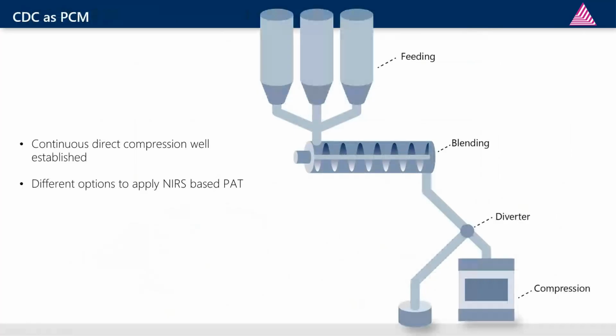We'll focus mainly on the continuous direct compression applications. They are very widely used meanwhile in the industry, and they get the most of the attention in the industry. I would not say there's still a lot of granulation and other high shear granulation and also roller compaction applications. But most of our work is really based at the moment on the continuous direct compression application. And there we have 3 different positions where we can actually measure the blend uniformity. First is directly at the blender or in the blender. Secondly, somewhere between the final blender and the tablet press, quite a common place as well. And then finally, BU in the feed frame of the tablet press. So these are the main positions where the instruments can be used in a CDC line.